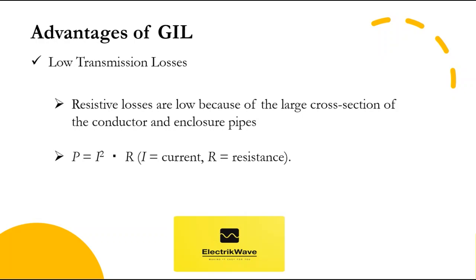GIL has low transmission losses. Resistive losses are low because of the large cross section of the conductor and enclosure pipes. Typical GIL resistances are 6 to 8 milliohm per kilometer, depending on the outer diameter — 500 mm or 600 mm — and the wall thickness of the enclosure and conductor pipe, 6 mm to 15 mm. The transmission losses are related to the square of the transmitted current as P = I²R. When the current rating is high, as it is for GIL — for example 3,150 ampere — the effect of low transmission losses is high. The losses through the insulating gas are negligibly small.